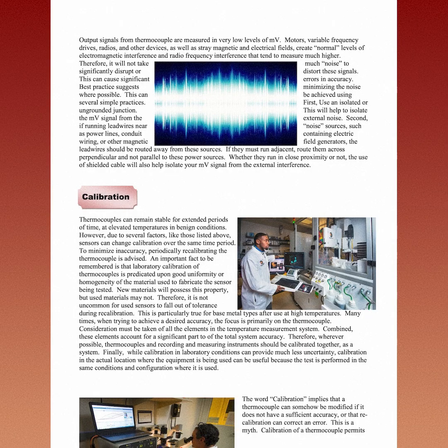Interference or noise. Output signals from thermocouples are measured in very low levels of mV. Motors, variable frequency drives, radios, and other devices, as well as stray magnetic and electrical fields, create normal levels of electromagnetic interference and radio frequency interference that tend to measure much higher. Therefore, it will not take much noise to significantly disrupt or distort these signals. This can cause significant errors in accuracy. Best practice suggests minimizing the noise where possible. This can be achieved using several simple practices.